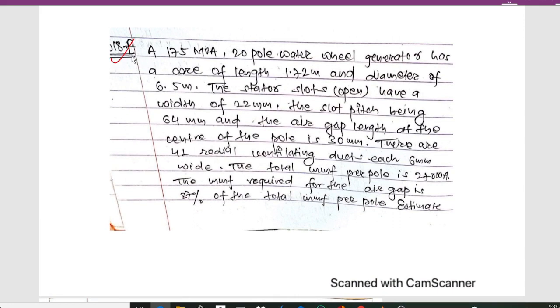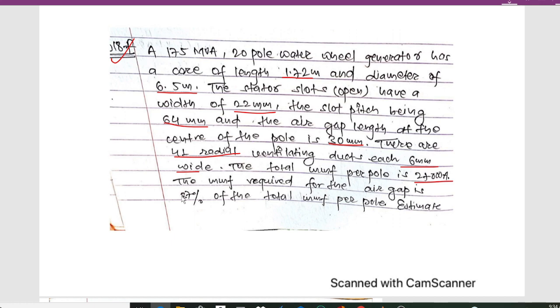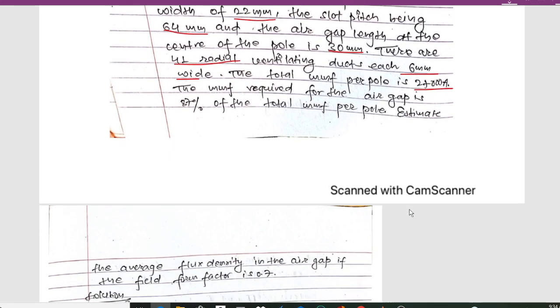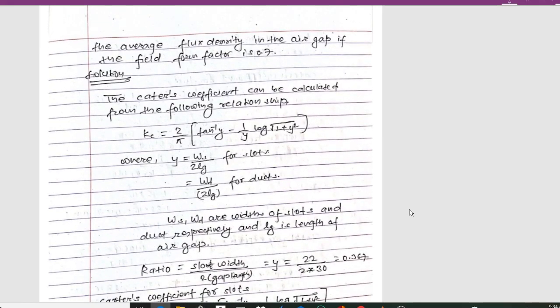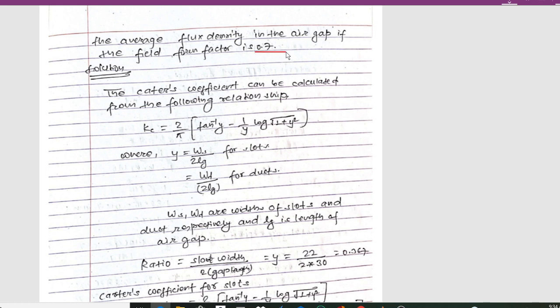The next numerical was asked in the 2018 fall exam. A 175 MVA, 20-pole water wheel generator has a core length of 1.72 m and diameter of 6.5 m. The stator slots have a width of 22 mm and slot pitch of 64 mm. The air gap length at the center of the pole is 30 mm. There are 41 radial ventilating ducts, each 6 mm wide. The total MMF per pole is 27,000 A, with the MMF for the air gap being 87% of the total. Estimate the average flux density in the air gap given a field form factor of 0.7.